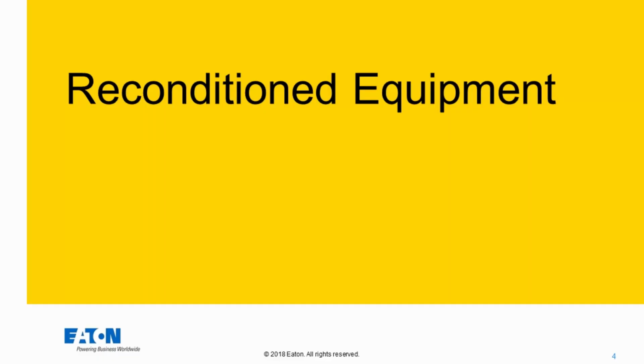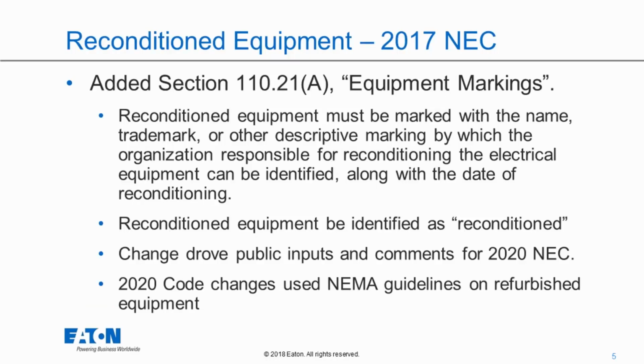So let's start with the reconditioned equipment. A little bit of history. Reconditioned equipment became a concern in the 2017 NEC when they added a section to 110.21(A) on equipment markings. Basically, they added a section that said reconditioned equipment must be marked with the name, trademark, or other descriptive marking by which the organization responsible for reconditioning the electrical equipment can be identified, along with the date of reconditioning.